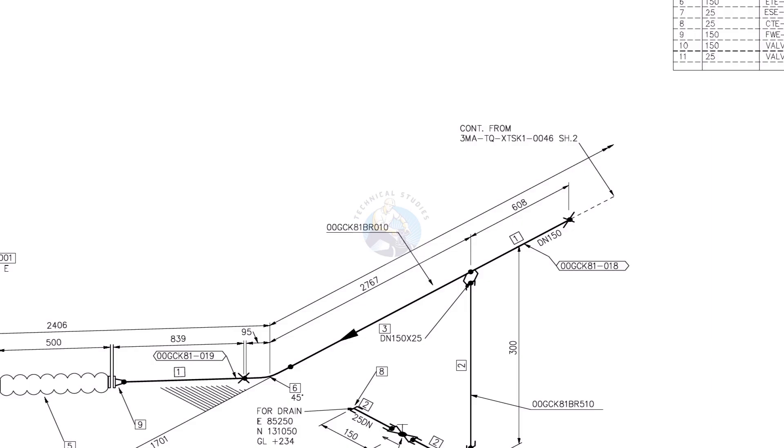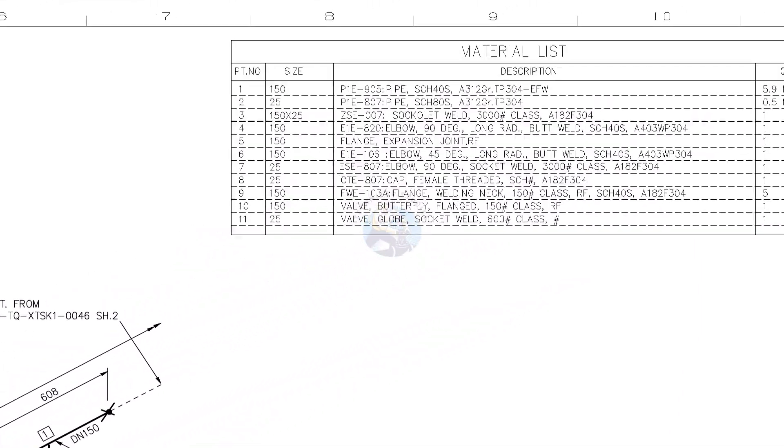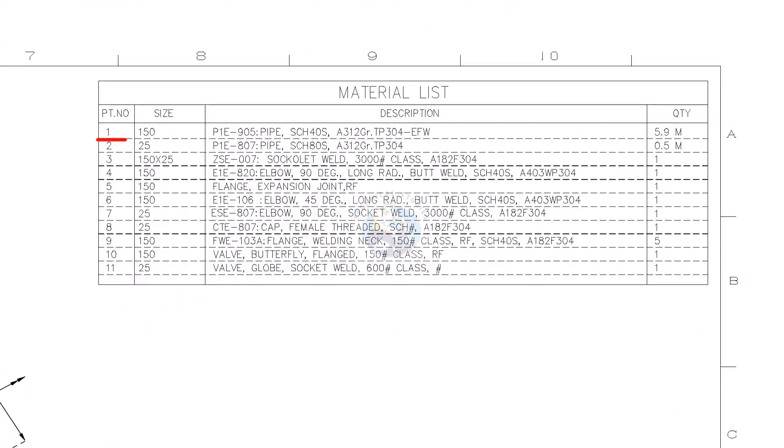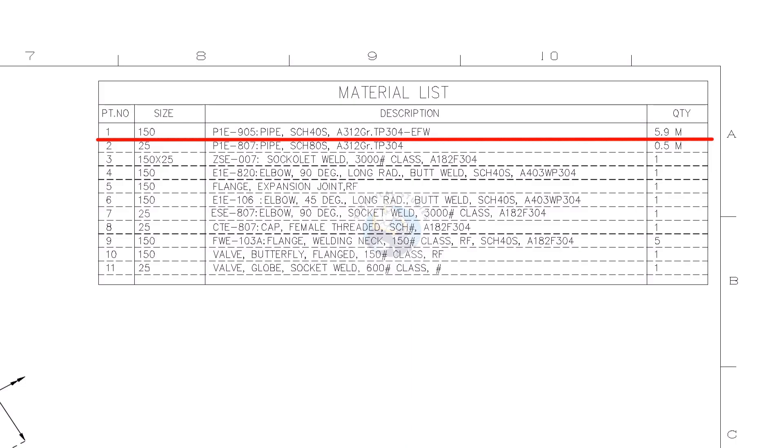Let us check the part list. PT means part number. Part number 1 is pipe, the size of the pipe is DN150 or 6 inches. Pipe schedule is 40S, grade A312, TP304. TP stands for tubular product.